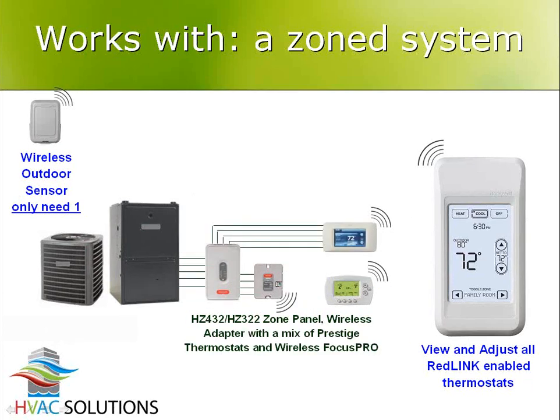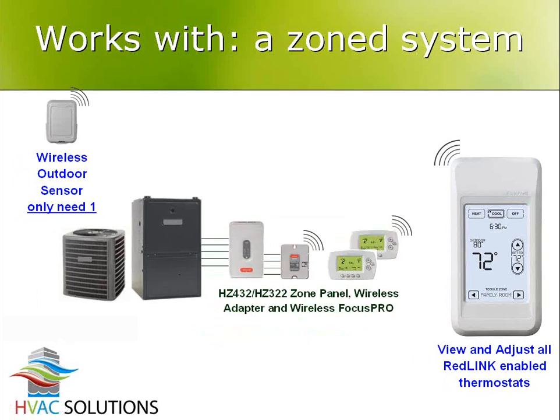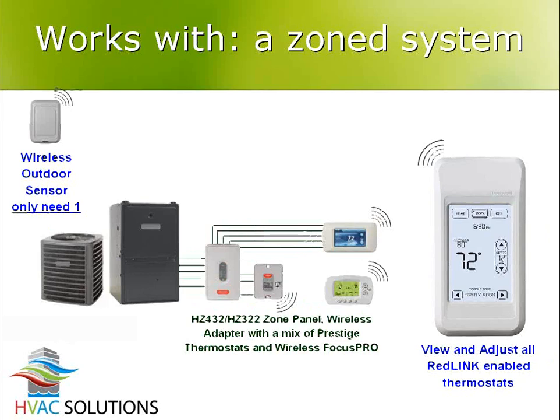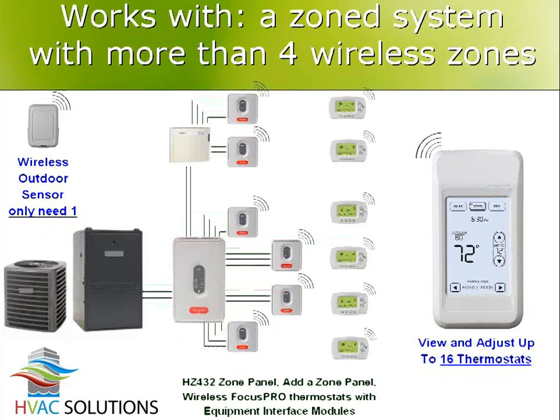And then if I go to the zone system and I want to have a Prestige IAQ, so in this example maybe I've got a Prestige IAQ, a regular Prestige stat, color touchscreen on my first floor, and on my second floor maybe I have a FocusPRO because it doesn't really matter as much because no one's upstairs. Downstairs I want to have the Prestige because I want my neighbors to see I'm cool and I have a color touchscreen stat. That guy hardwires down to the zoning panel, but then the other zones upstairs or wherever they're at talk wirelessly into the equipment module. So if they're all FocusPRO, it's wireless from the stats down to the basement. If it's Prestige and FocusPRO mixed, then the Prestige has to wire downstairs, but all the FocusPROs talk wirelessly. So I might have one Prestige and then have 4 FocusPROs for the other zones or something like that. And it can get pretty complicated, and you can get as hairy with it as you want.